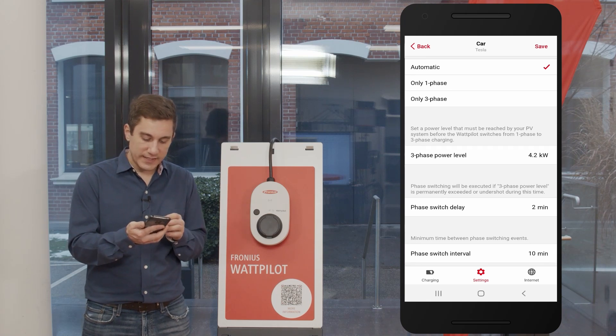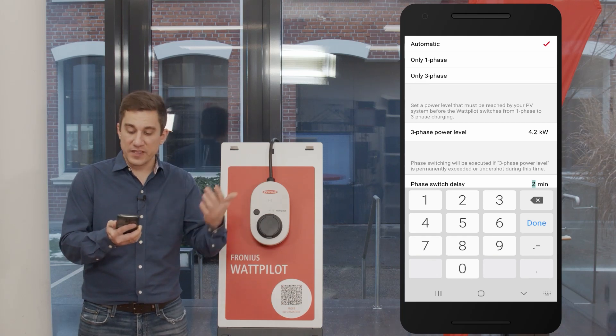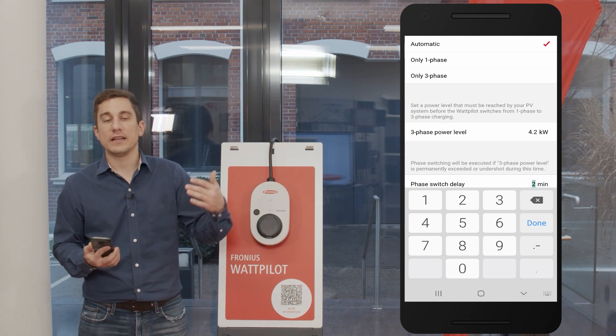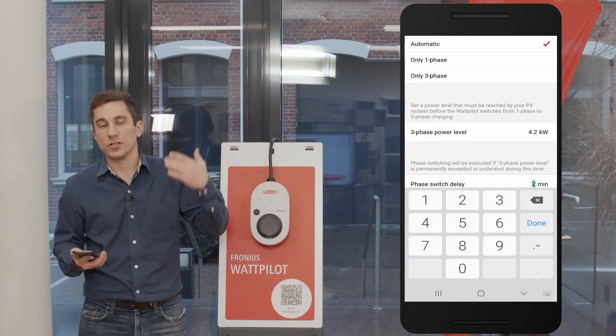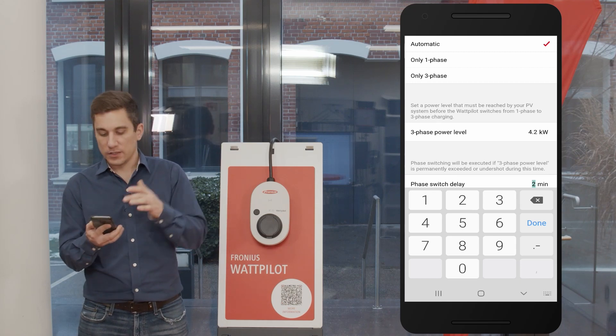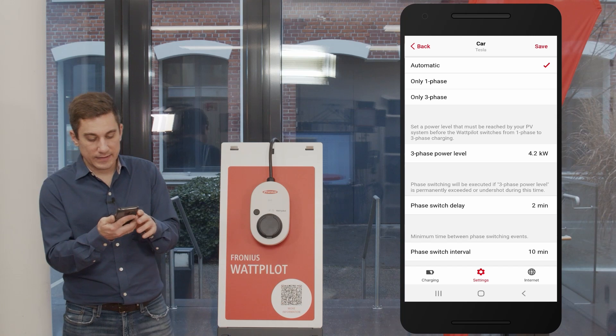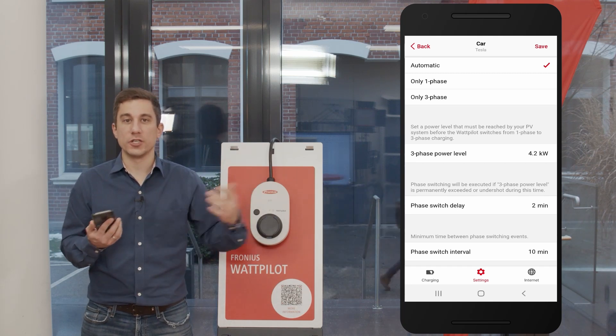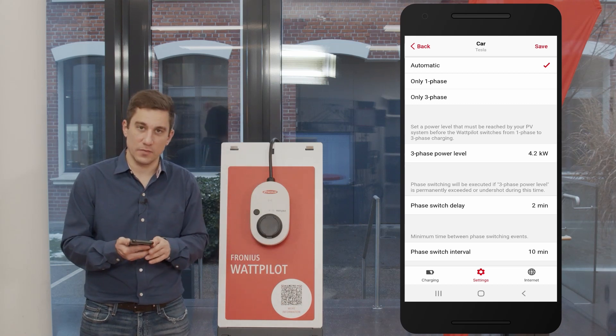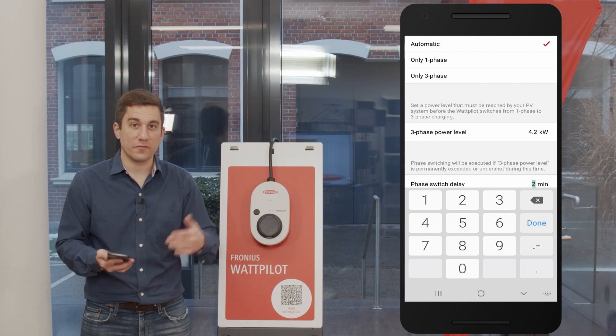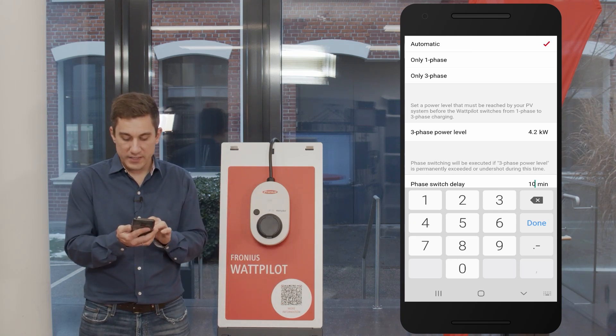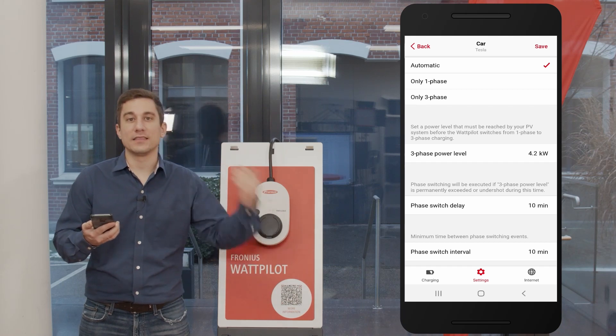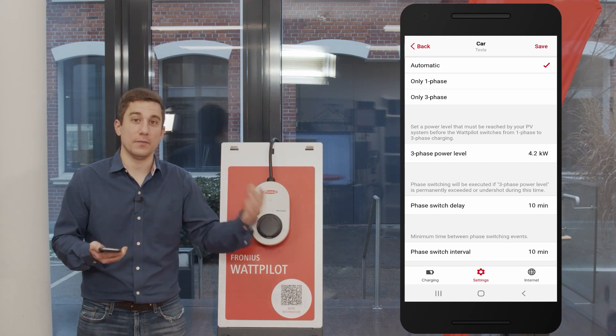The phase switch delay determines how long the Wattpilot waits before performing a phase switch. It is factory set to two minutes, meaning the Wattpilot waits two minutes before switching phases. This helps avoid switching to three phase prematurely when there may not be enough sustained PV surplus energy. If you want to ensure you really have enough power — for example in the morning hours — you can extend this period, for example to 10 minutes, so the Wattpilot waits longer before switching to three phase.